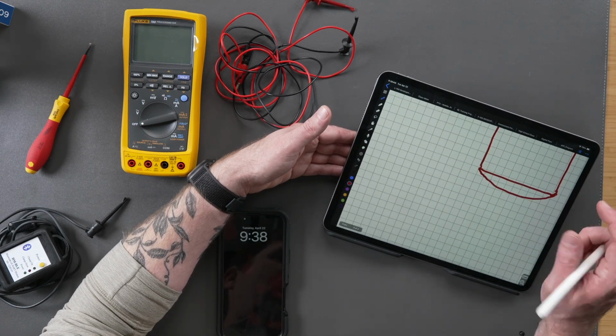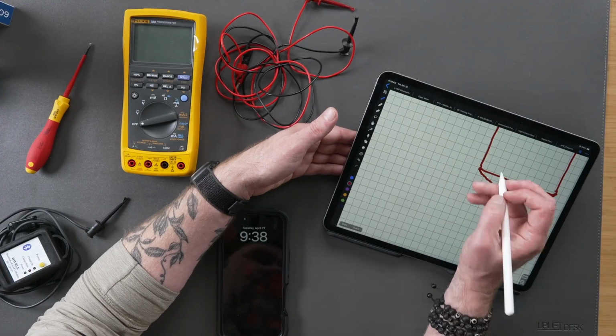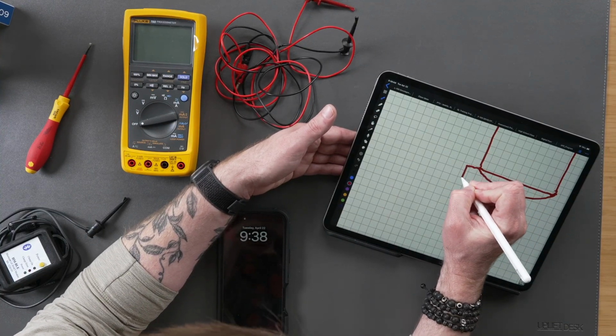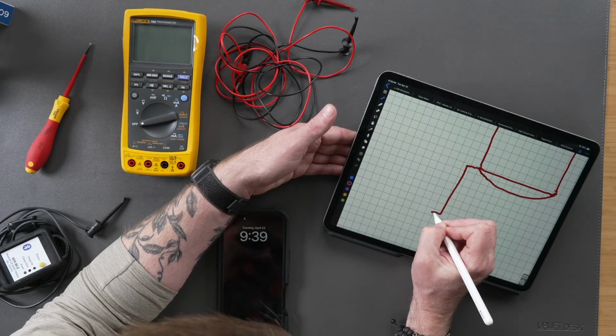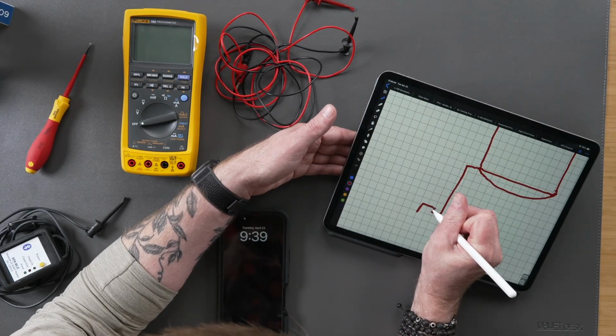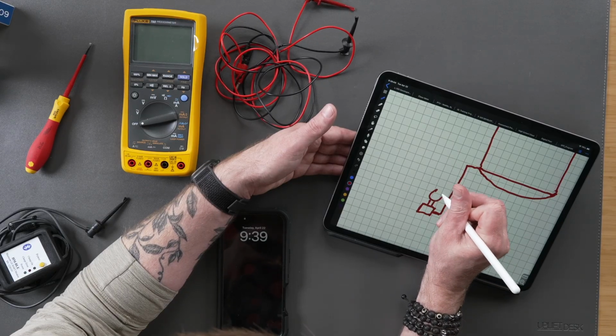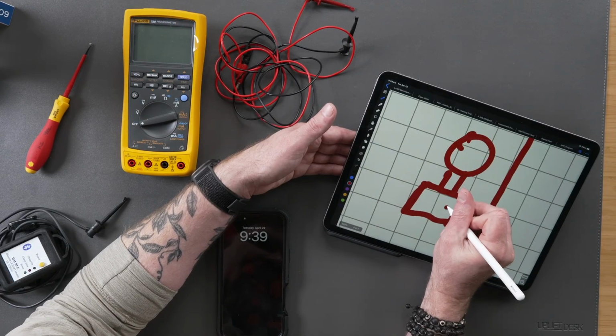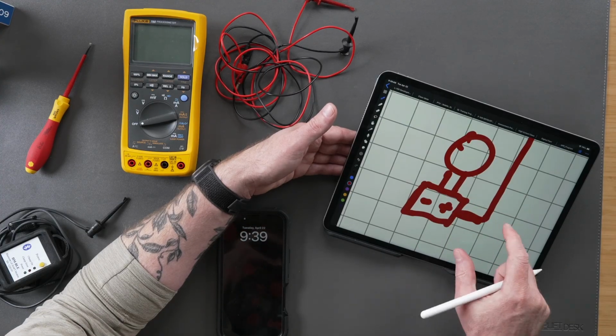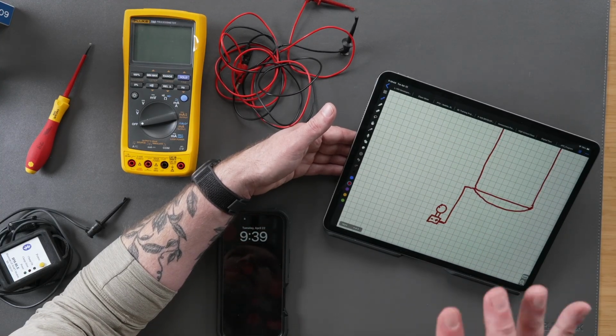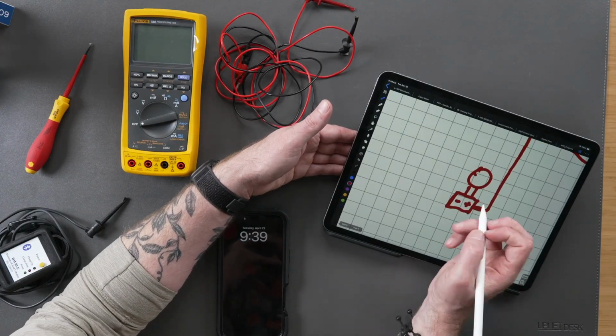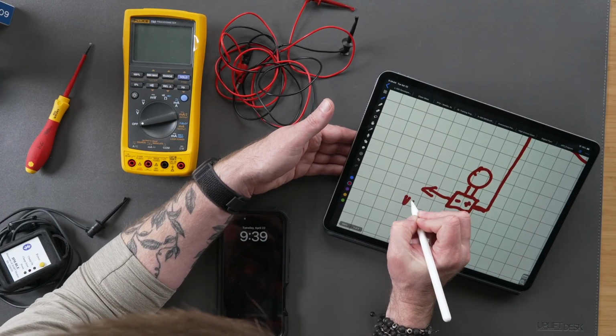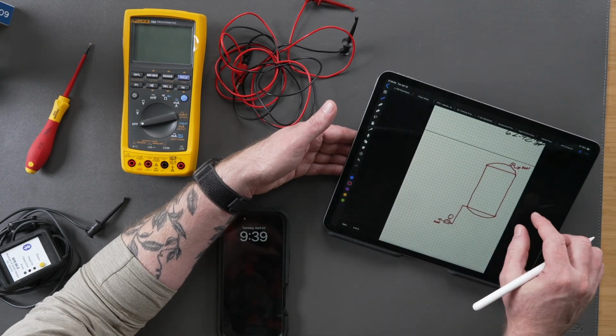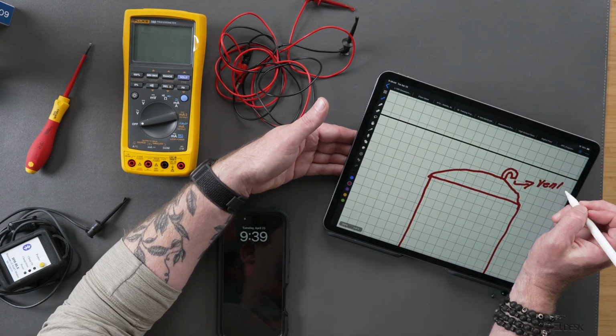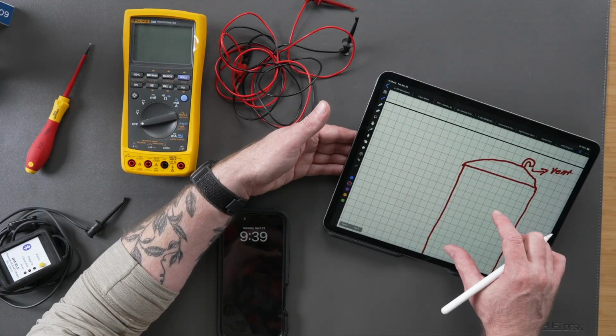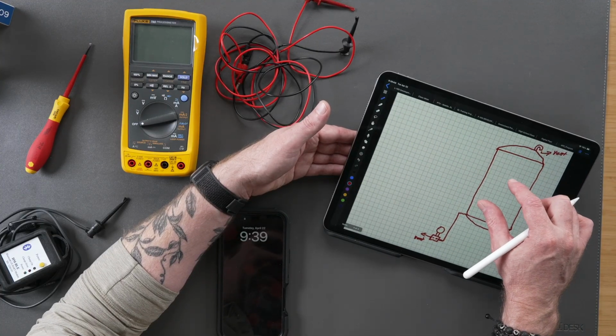Let's say our pressure transmitter is actually mounted below the high pressure tap point. So let's say it comes down here. There's my differential pressure device right there. And I have a high side, I have a low side. So what we're going to do when we go out there and put it onto the vessel is vent this side to atmosphere, same as we had here. I've got that vented to atmosphere at the top. I've got the bottom vented to atmosphere as well.